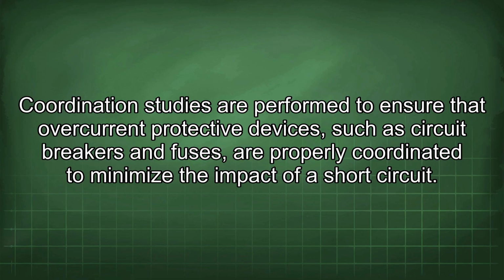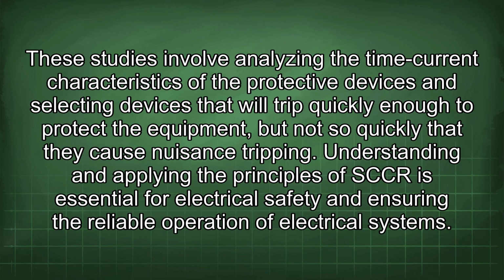Coordination studies are performed to ensure that overcurrent protective devices such as circuit breakers and fuses are properly coordinated to minimize the impact of a short circuit. These studies involve analyzing the time current characteristics of the protective devices and selecting devices that will trip quickly enough to protect the equipment, but not so quickly that they cause nuisance tripping. Understanding and applying the principles of SCCR is essential for electrical safety and ensuring the reliable operation of electrical systems.